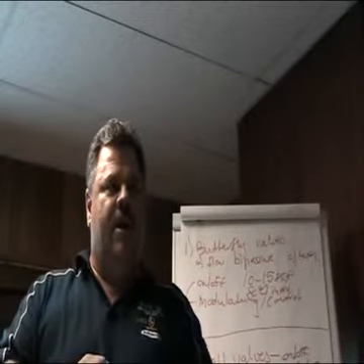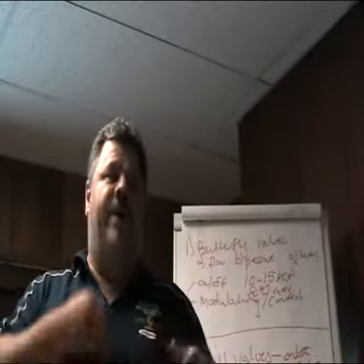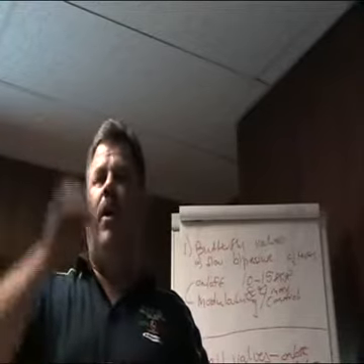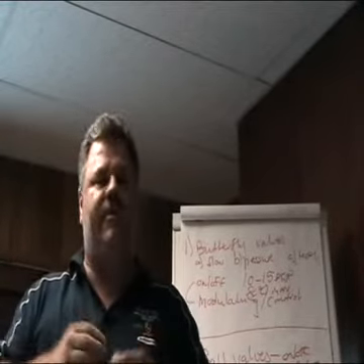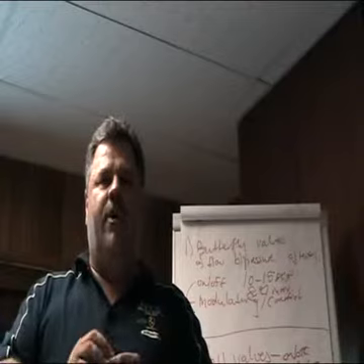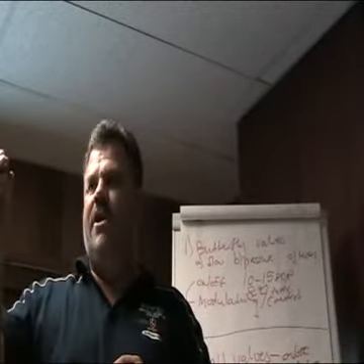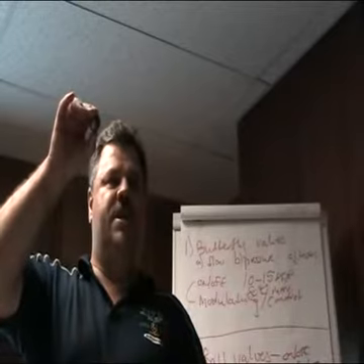If you go full bore. Correct. That's another discussion. You get full bore and reduced bore. That just means, quickly, for somebody who's interested in that, when you have a 4-inch line, 100 millimeters, you've got a 4-inch valve in there. So when this valve opens, this is your line. The flow that it can pass is equal to the flow that the pipeline can handle.